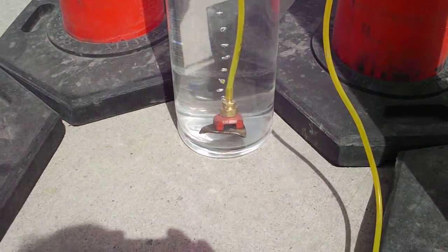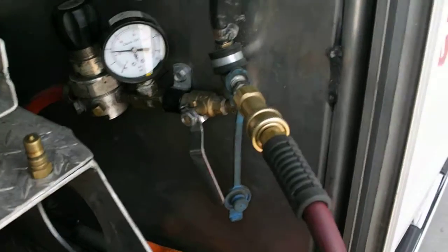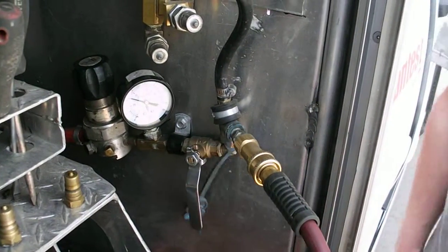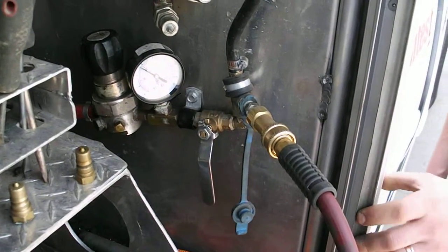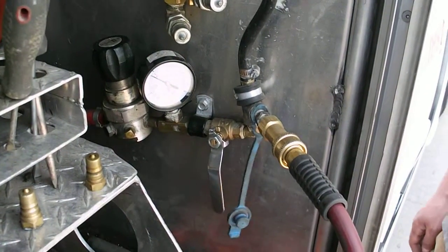The bubbler is not going to move with that kind of turbulence. Typically, close that up again, sort of repressurized — do a couple second, half a second quarter valve rotation. There you go. That's all that's required to repressurize the hose.